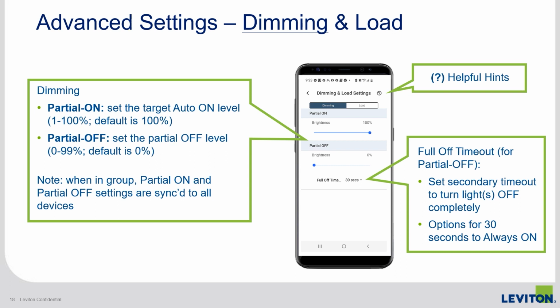Partial off can also be set on this page if required. Once a space is vacant and the timeout expires, lighting will dim to this level rather than going all the way off. There's a drop-down bar to set the partial off timeout where the lights will turn full off after this period. The timeout options range from 30 seconds to always on. This can be used in an application requiring lights to be on at some level for safety reasons, such as a stairwell or dimly lit long hallways or corridors.